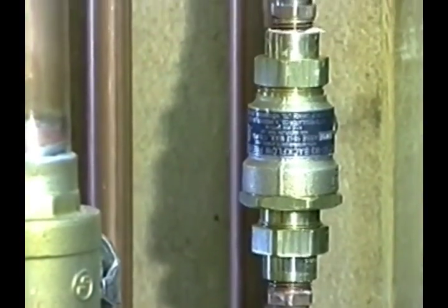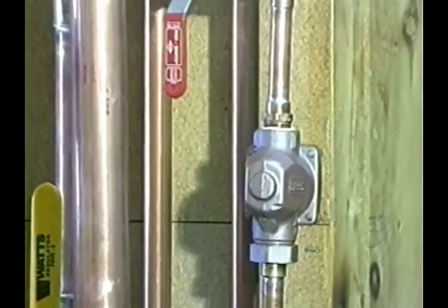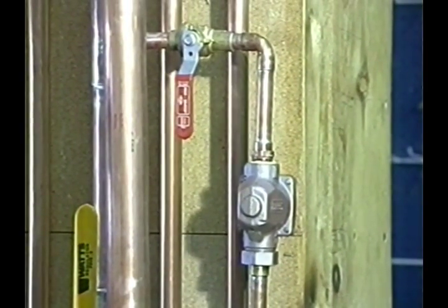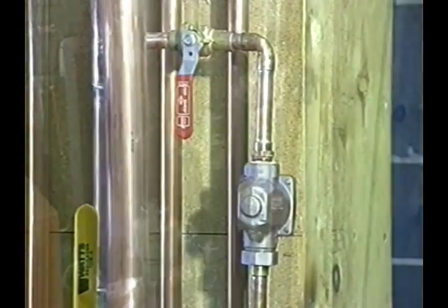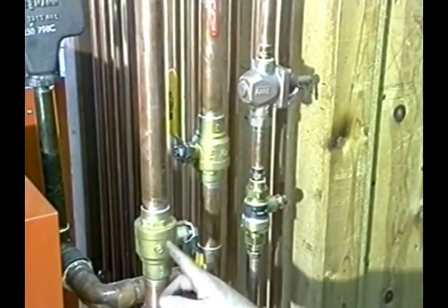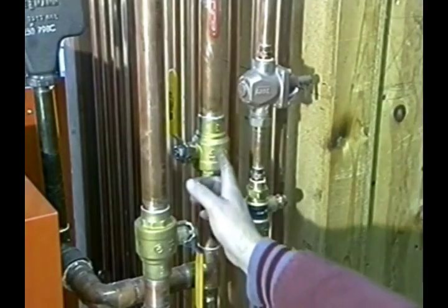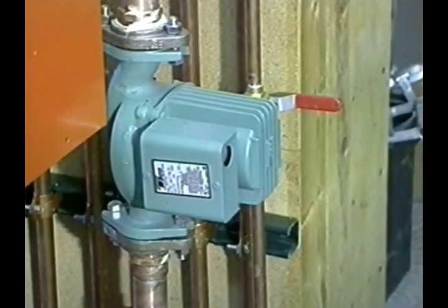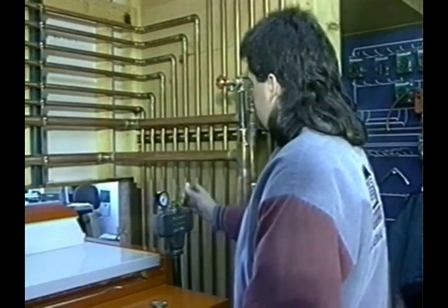Next, install a backflow preventer and a fill valve. This supplies the boiler system with water as well as preventing any contamination between boiler and domestic water. When you begin piping from the supply and return side of the boiler, it's a good idea to install ball valves to isolate the boiler from the rest of the system. Most pumps on a boiler come pre-wired and include isolation ball valves.